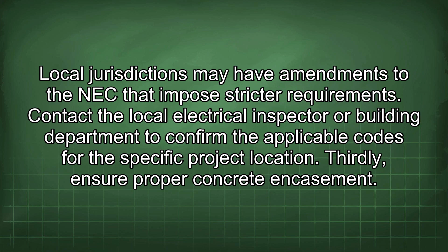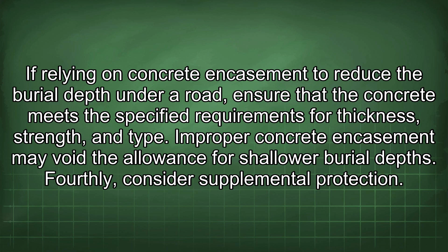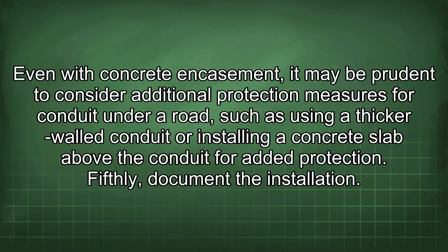Thirdly, ensure proper concrete encasement. If relying on concrete encasement to reduce the burial depth under a road, ensure that the concrete meets the specified requirements for thickness, strength, and type. Improper concrete encasement may void the allowance for shallow burial depths. Fourthly, consider supplemental protection. Even with concrete encasement, it may be prudent to consider additional protection measures for conduit under a road, such as using a thicker walled conduit or installing a concrete slab above the conduit for added protection.